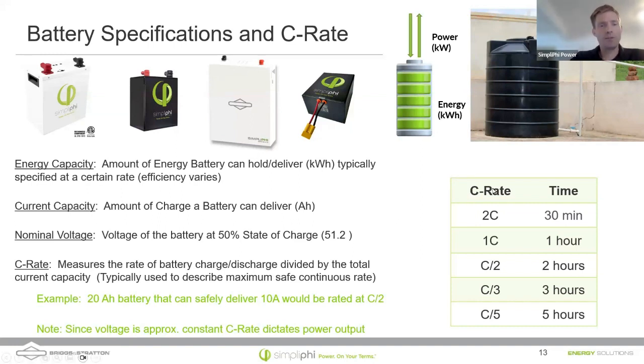All right, so what is a C rate? A C rate is the rate at which a battery is charged or discharged divided by the total current capacity of the battery. Typically it's easiest to understand a C rate in terms of how long it would take to discharge a 100% charged battery. A C rate of 1 C would mean you would discharge a battery in 1 hour. A C rate of 2 C is twice as fast, and would discharge a battery in 30 minutes.